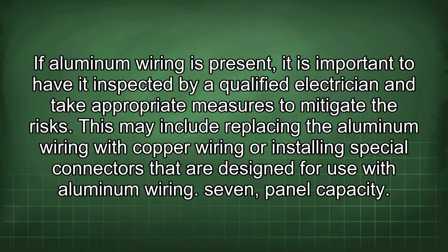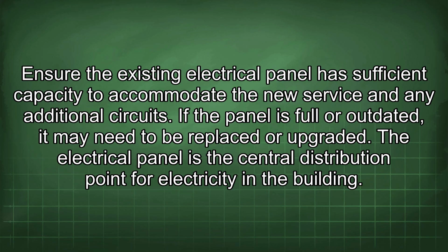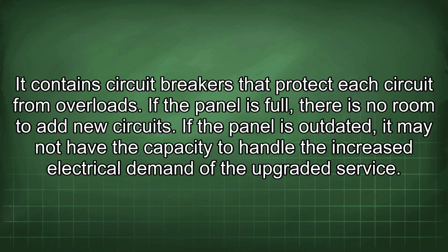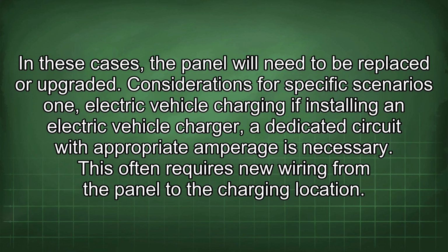7. Panel capacity. Ensure the existing electrical panel has sufficient capacity to accommodate the new service and any additional circuits. If the panel is full or outdated, it may need to be replaced or upgraded. The electrical panel is the central distribution point for electricity in the building. It contains circuit breakers that protect each circuit from overloads. If the panel is full, there is no room to add new circuits. If the panel is outdated, it may not have the capacity to handle the increased electrical demand of the upgraded service. In these cases, the panel will need to be replaced or upgraded.